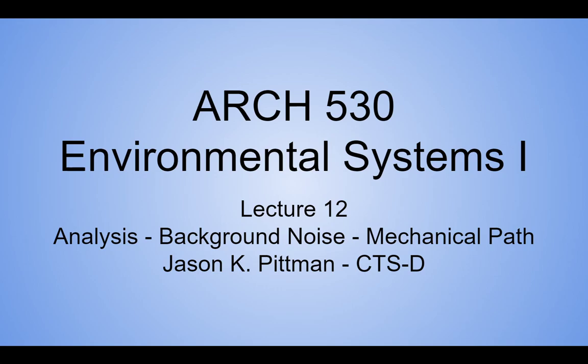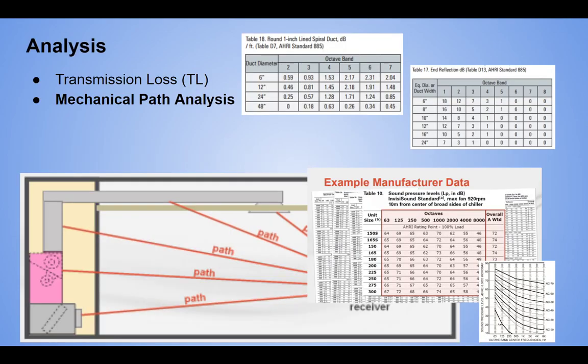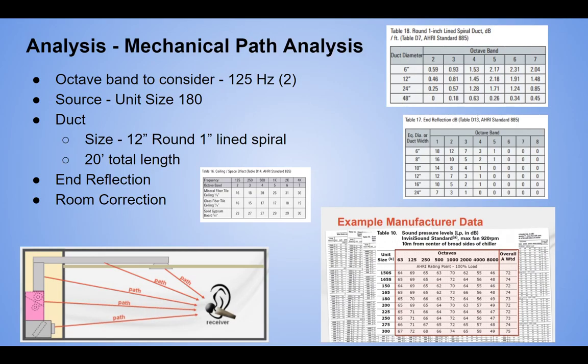What we've done previously is looked at transmission loss. We basically looked at three pathways. We were assuming this was in the space and we weren't worried with the issue of breakout noise. Now we're doing the final one. We're looking at this diffuser, what the level is at this diffuser and what the diffuser noise contributes to NC. For the sake of simplicity and not to do this 15 or 20 times over, we're just going to look at the 125 hertz octave band, octave band number two.